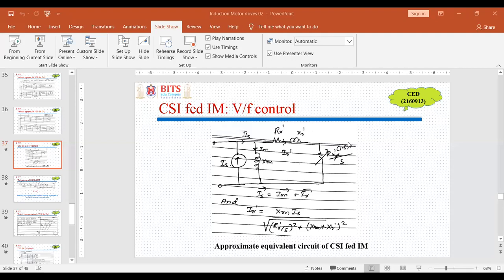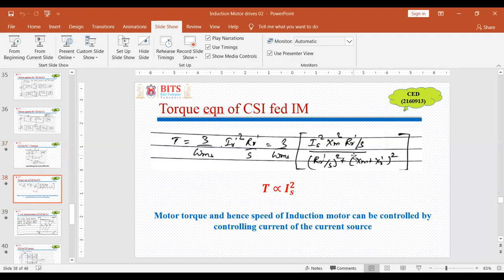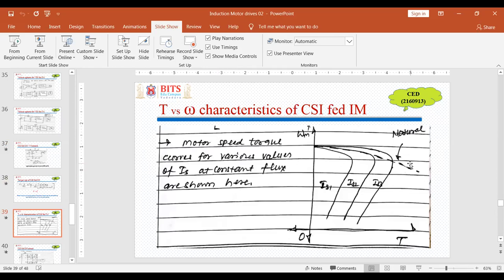Welcome everybody. Yesterday we were discussing about CSI-fed induction motor drive and this is the approximate equivalent circuit where we can replace the voltage source by a current source. We can show that rotor current is directly proportional to the source current, and in this fashion the torque equation in terms of a current source shows that torque is proportional to current squared. So in short, a current source can control the motor, and this is how we get different characteristics for different source currents.